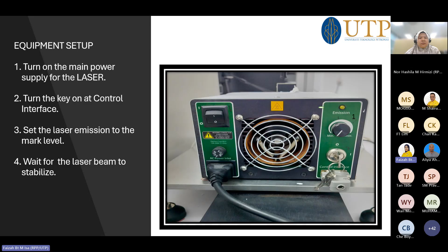This is our equipment setup. Firstly, turn on the main power supply for the laser at the top left side. Number two, I turn the key on at the control interface at the below right side. Then set the laser emission to the marked level. Usually I use level 1. Then wait for the laser beam to stabilize. Allow around 30 minutes for warm up.